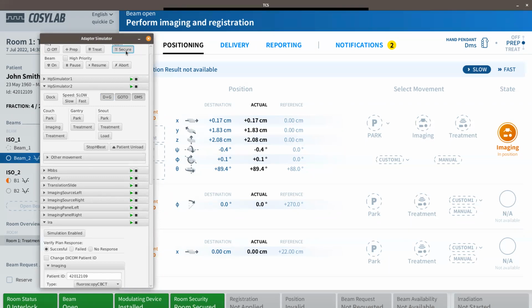The reason for acquiring CT image is the following. So we are currently using the treatment plan that was generated based on some so-called primary CT image. After that, we position the patient to the table as precisely as we were able to. And now we will acquire another CT image, the so-called secondary CT image. And we will use another piece of software called image registration software that will compare those two images and calculate the offset between them. And this offset between those two images is called correction vector.